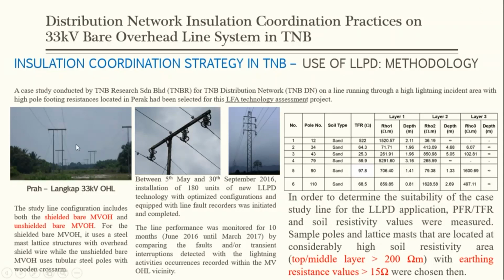Right? In order to determine the suitability of the case study line for the LLPD application, the PFR or TFR and soil resistivity values were measured. Sample poles and lattice masts that are located in considerably high soil resistivity areas, where the top or middle layer is more than 200 ohm meter, and earthing resistance values of more than 15 ohms were chosen. Okay, because we want to prove the hypothesis that the LLPD works in an area with high lightning density and at a high earthing resistance value.